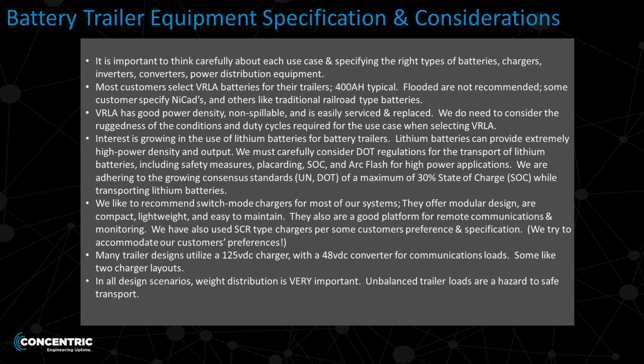Our early trailers were typically 200 amp hour. We're seeing now people looking for 400, even 600 amp hour. Our recommendation is VRLA - we don't recommend flooded batteries. We have some users who insist on NiCad batteries, so we don't argue with good customers, and we've done trailers with NiCads. A couple of customers also like those traditional railroad type batteries, so we've used those as well. But VRLA is the norm.